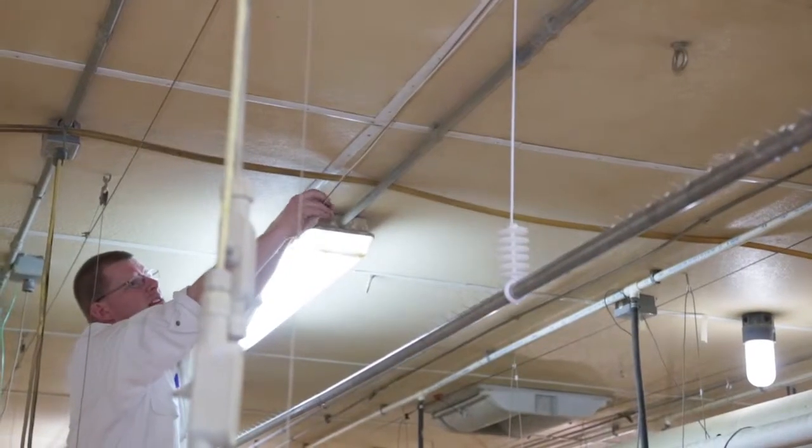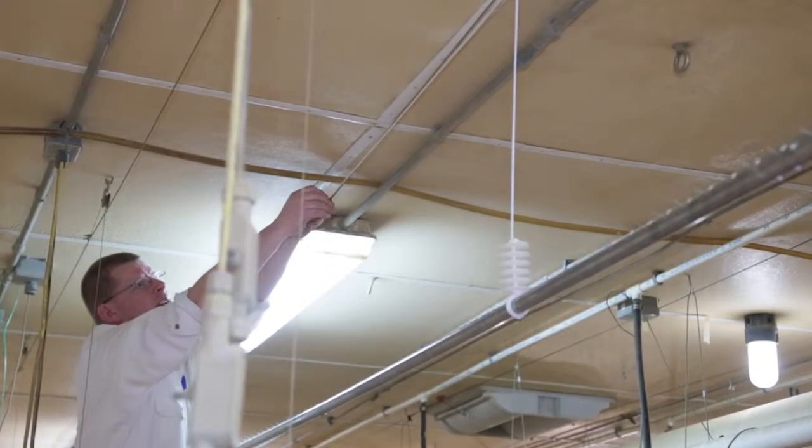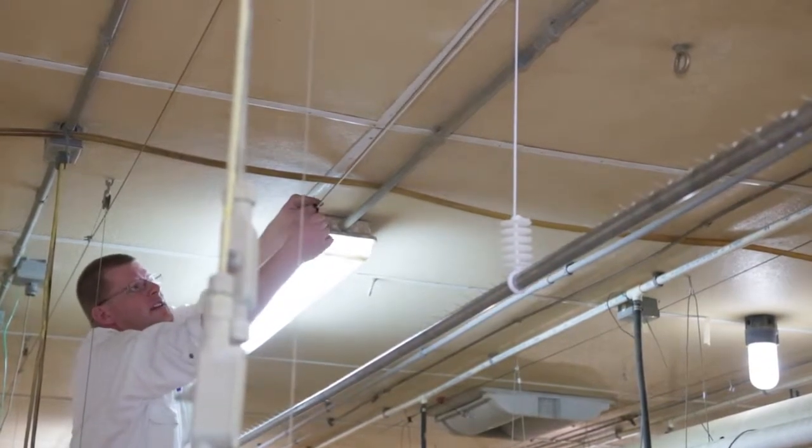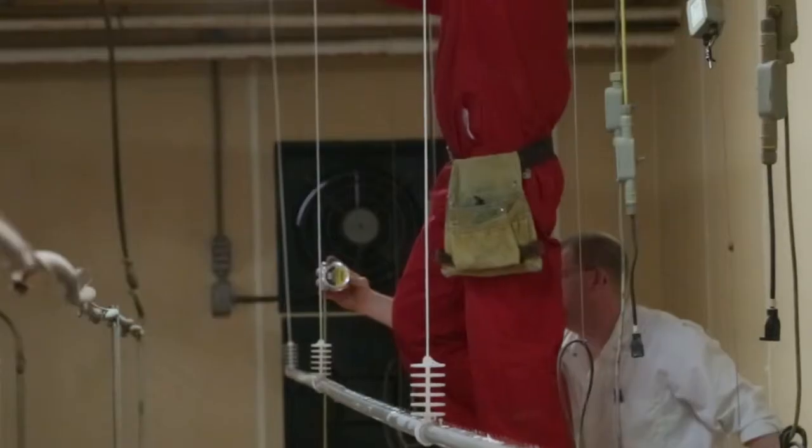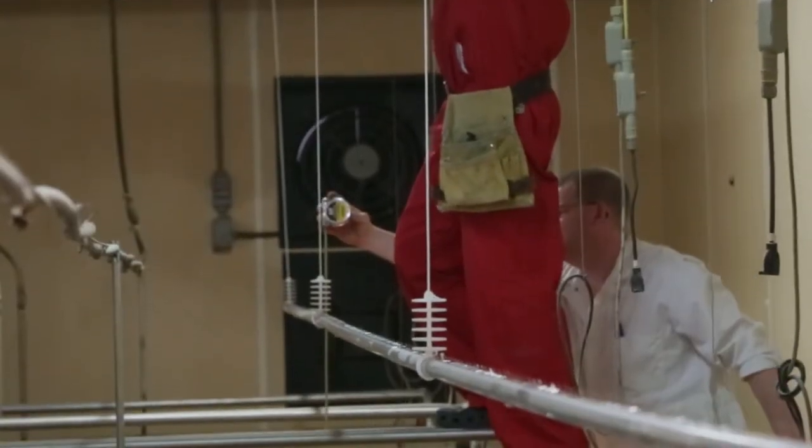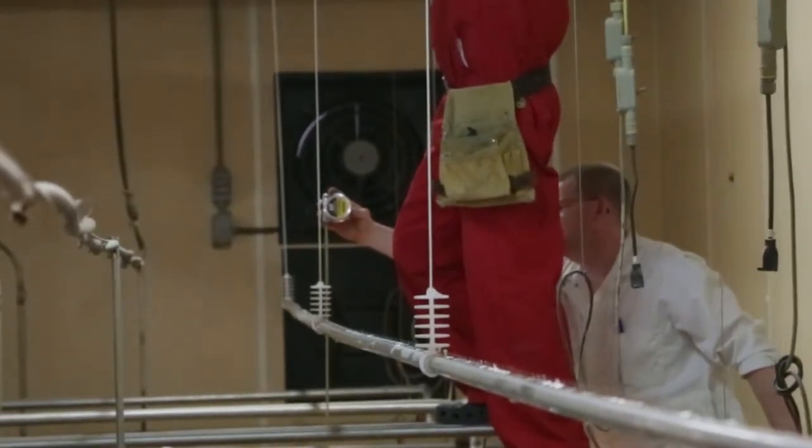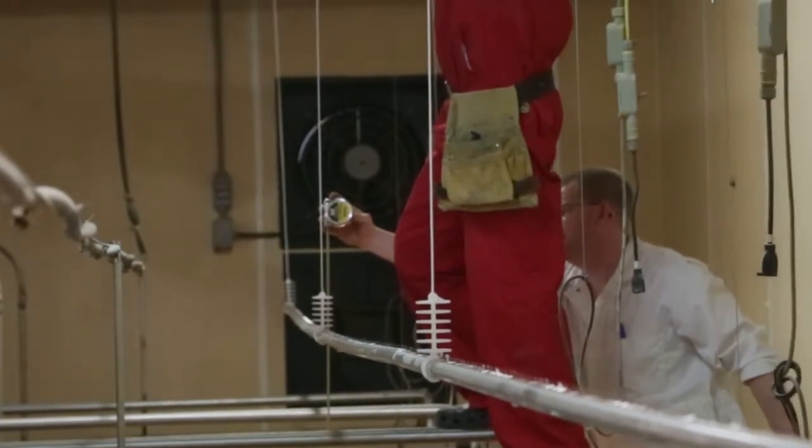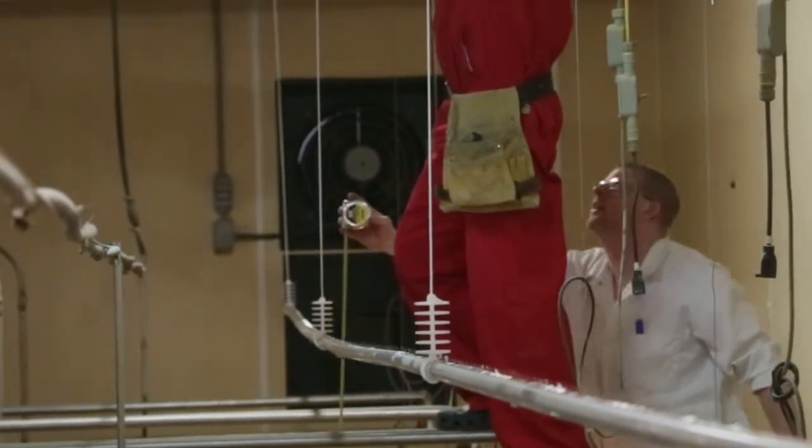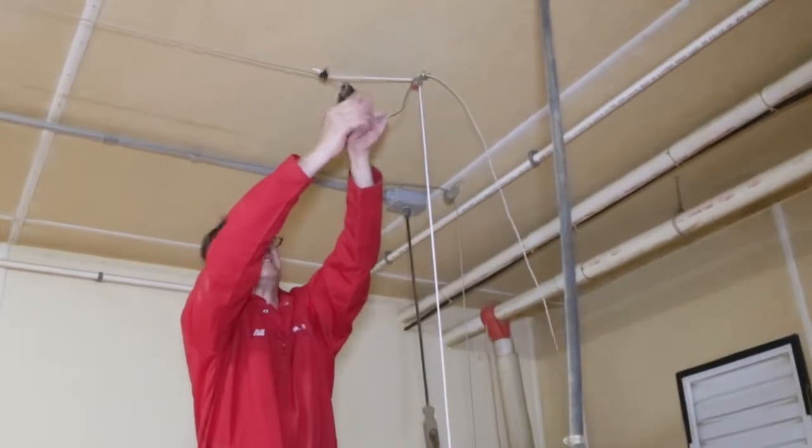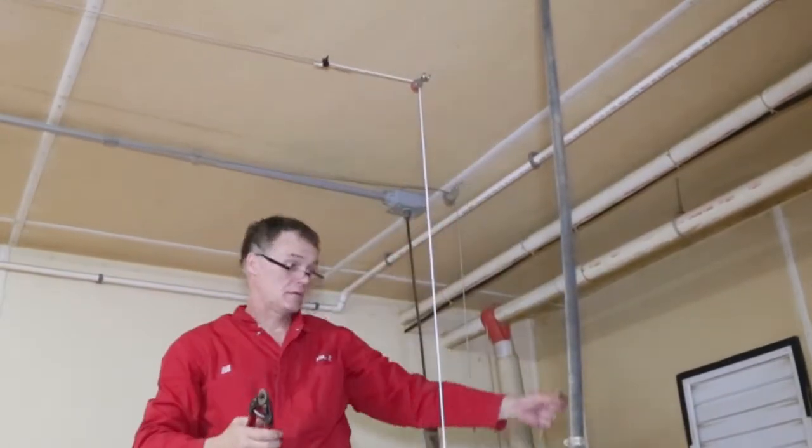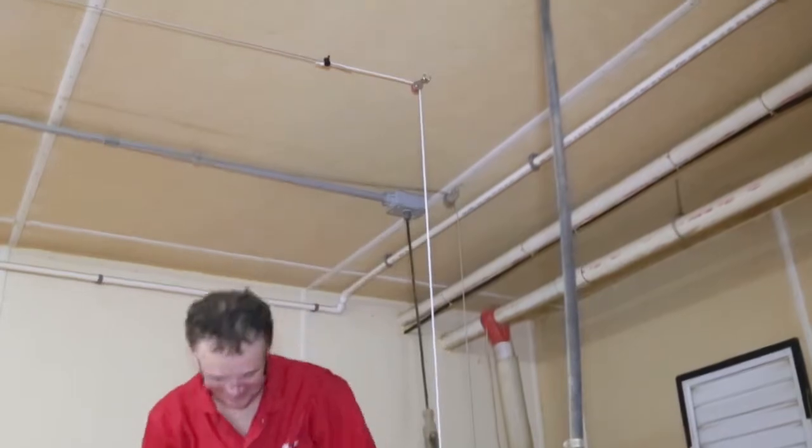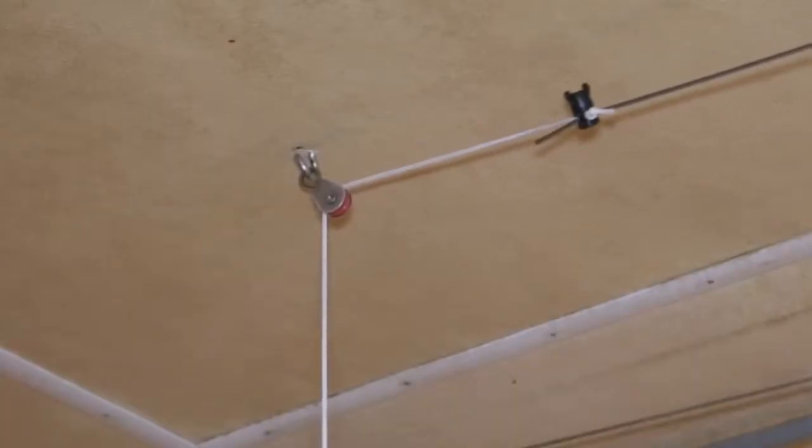Attach the ropes to the pull cable using a curtain thumb nut. Tension the rope and the pipe insulator. Start at the rope nearest the winch. Slide the thumb nut towards the winch. At the furthest, last support of the corona pipe run, attach the rope to the cable. Remove the weight and trim the cable. The cable should not extend through the pulley.